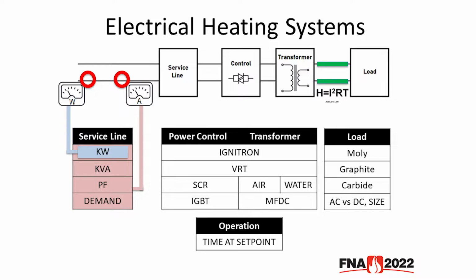The first part of an electrical heating system is the power controller. Historically, ignitron tubes, used prominently in the 30s and 40s, were really just rectifiers to control power to an application. Another type of power supply is the VRT, or Variable Reactance Transformer, which is actually a control and transformer in one. The core in a VRT can be electrically desaturated or saturated to control power. Finally, there are the more sophisticated control systems like the common-day SCR and IGBT control types.